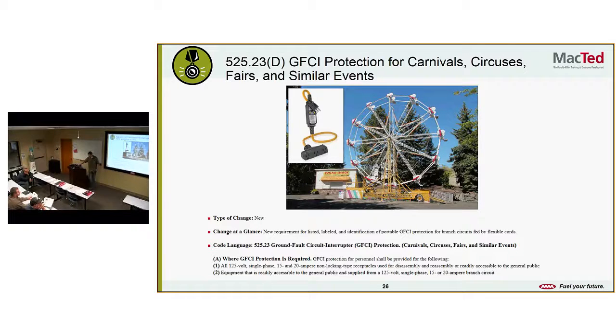Yeah, I got speed. New requirements for listed, labeled, and identification of portable GFI protection for branch circuits fed by flexible cords. When GFI protection is required, GFI protection for personnel shall be provided for the following: all 125 volt single phase 15 and 20 amp non-locking type receptacles used for disassembly and reassembly that are readily accessible to the general public. Equipment that is readily accessible to the general public and supplied from 125 volt single phase 15 and 20 amp branches. So if you have to be a carnival assembler during the summer, be on the lookout for GFIs. Those are now required. If you're looking for any side work.